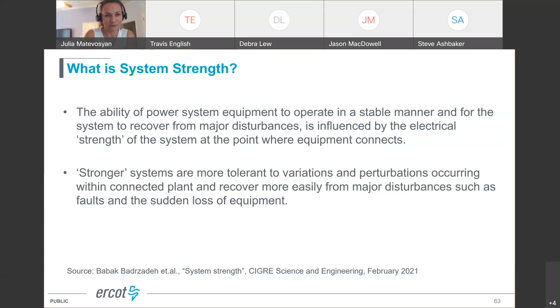There is a limit on how much conventional grid-following inverter-based resources can be accommodated because of system strength concerns, and also on a wider grid level because of frequency stability concerns. To address this, system operators may limit output from inverter-based resources and supply the remaining load with synchronous generation to ensure that sufficient system strength and inertia are provided. As I mentioned in my previous presentations, this is being done, for example, in Australia, Ireland and Texas. It's implemented in different ways, in how it's enforced, but the overall goal is the same. Such operational constraints in the long run will impact output from inverter-based resources and may impede further development of these resources, making them uneconomic.